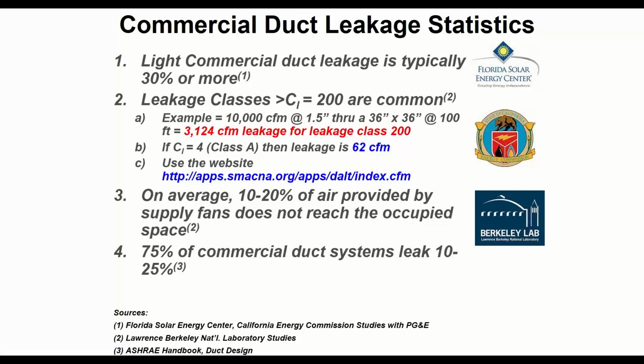This is just showing you some examples here for those that are familiar with some of the specifications associated with duct leakage. A really common specification listed here, as we're showing, is a 200. What that actually means is, an example with a 10,000 CFM air handler at 1.5 inches of static, you're allowed to have 3,100 CFM of leakage, and that's fine. That's acceptable. That's a third of your air, obviously, or almost a third of your air.